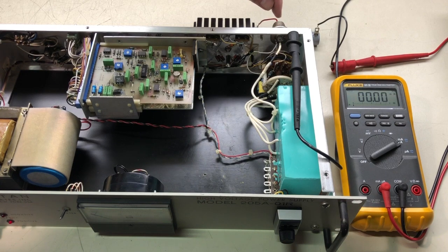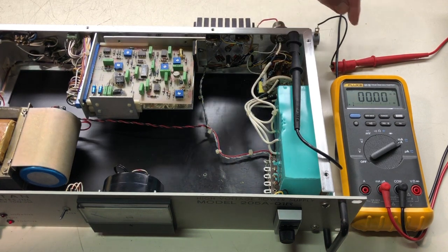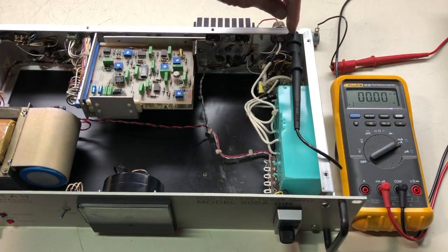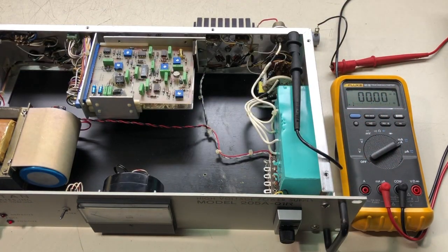It's on the meter side, so we come out through the high voltage on the connector, through the resistor, on the other side of the resistor, through the meter, and then ultimately to the ground connection. So with Ohm's law, we can figure out what the current will be. If we set for 375 volts and a 25 k ohm resistor, we'll get 15 milliamps at that 375 volts. So 15 milliamps will be the mid-scale, mid-range on this power supply. This power supply is rated 30 milliamps maximum. So with that 375 volts and 15 milliamps, that's a 5.6 watt load on the power supply. And again, resistor is rated 55 watts, so no problem there.